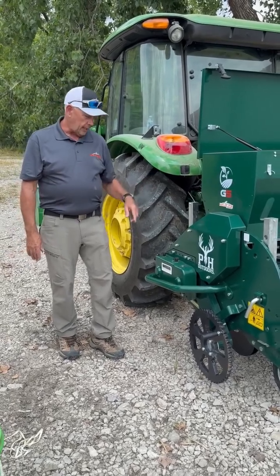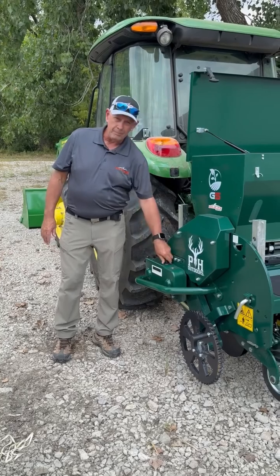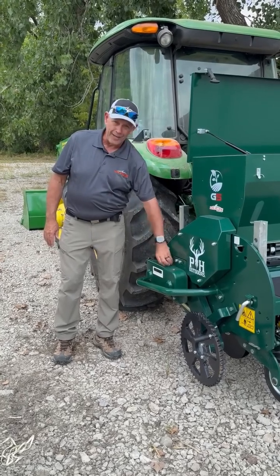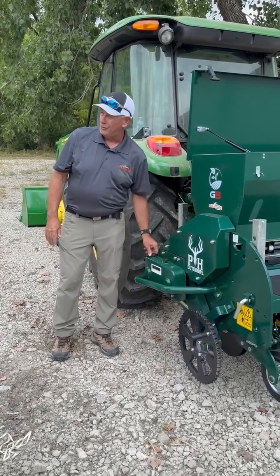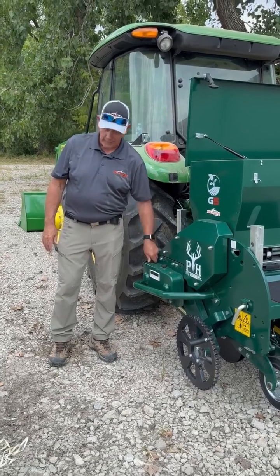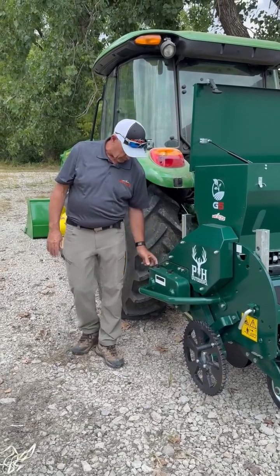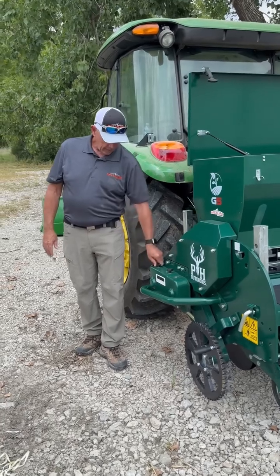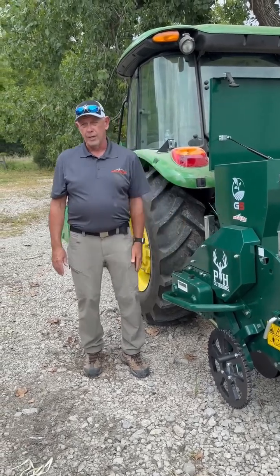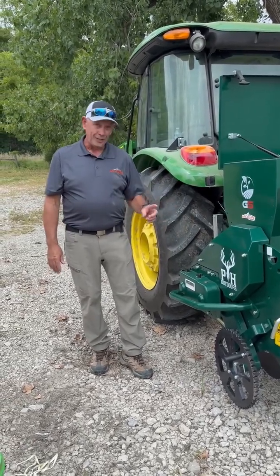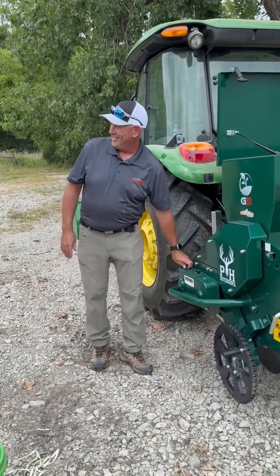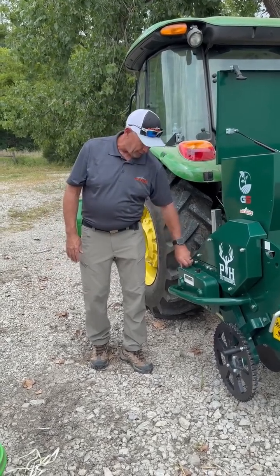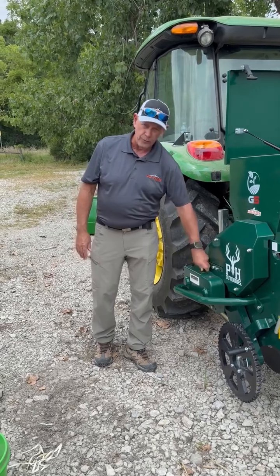One thing I want to tell you guys is these set screws on top - once you get your setting, you need to move the set screws down so it doesn't change while you're out in the field. It doesn't vibrate around much because it's on a knob, but always set your set screws down once you've got your setting. And loosen them up when you want to move it, because once you've got them set and you crank on it, you're just putting a lot of pressure on the whole system.